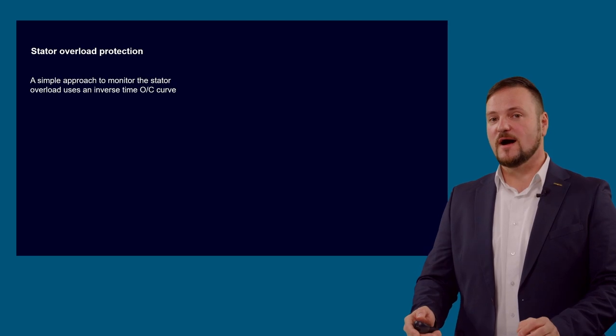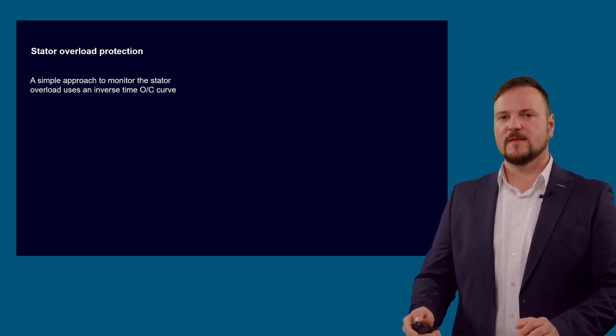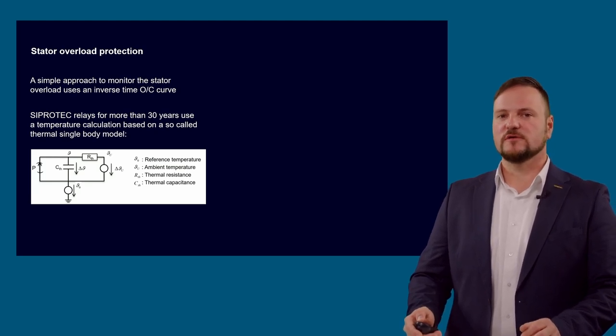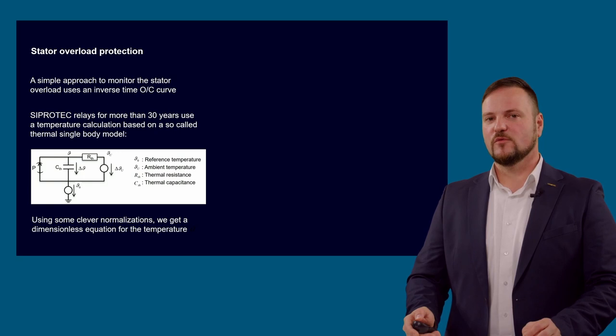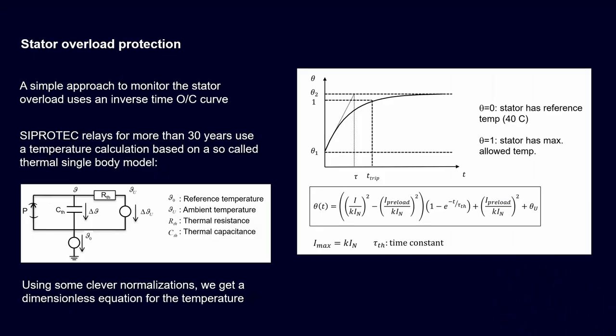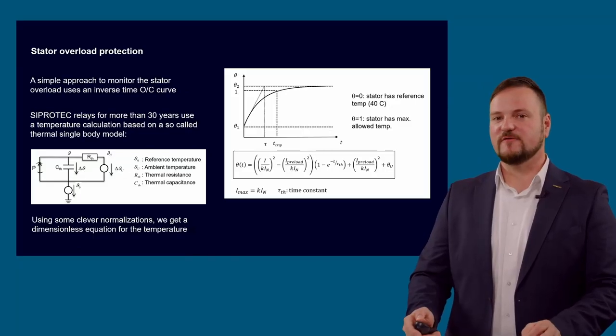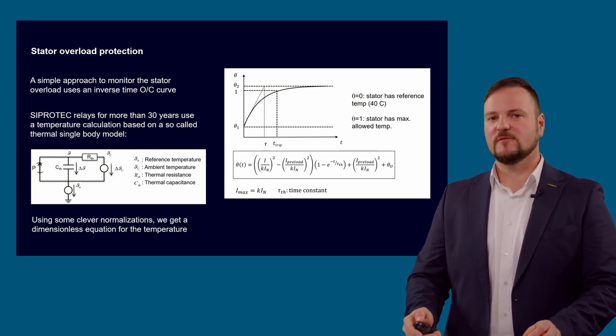The stator can be overloaded. The stator can be overloaded if the motor current is too high for a longer time. This happens, for example, when the motor voltage is below the nominal voltage, or for a longer time the load is too high. A simple approach to monitor the stator overload uses an inverse time overcurrent curve. The SIPROTEC relays for more than 30 years use a temperature calculation based on the so-called thermal single-body model, as shown below, considering the power source, the capacitance which heats up by one part of this power, and the thermal resistance which dissipates the other part of this power. Motor manufacturers do not deliver this parameter, but a clever simplification of this model can be used to monitor permanently the stator temperature and use the data which is available by the motor manufacturers.